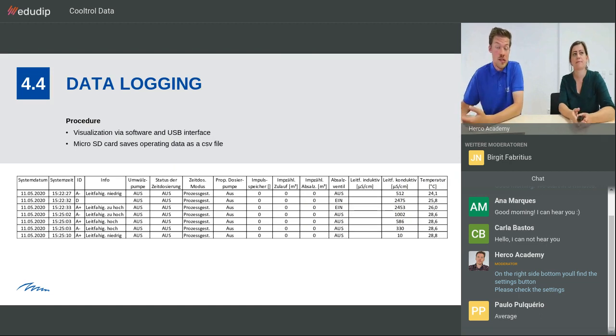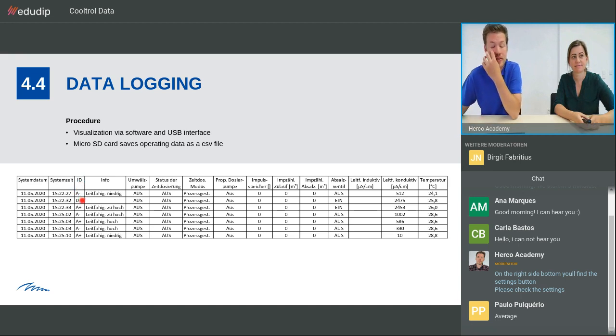All right, so here you see the logging file. It's actually in German, but it is like that. So we have the date and the time. Then also the ID. If there's nothing, it's a D, so this is normal operation. If there is a fault, then you see A plus, so the fault comes. And if you acknowledge the fault afterwards, it's A minus, so this means the fault goes.